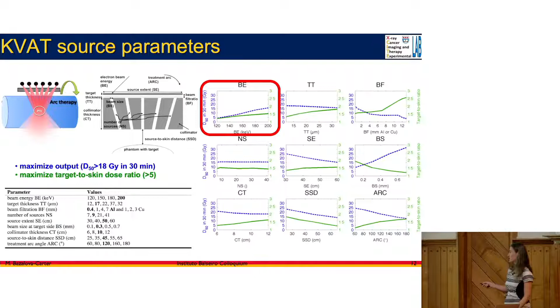But we basically concluded that beam energy played a big role. So this is just D50, maximized D50, maximized target to skin ratio. In green, D50 in blue. We found out that the higher the beam energy, the better the beam output, and the higher the target to skin ratio. So that wasn't surprising, right? If you go all the way to 6 MV or 15 MV, this is going to be even better, but we would have to use a different technology. So we knew we wanted to maximize that, but of course it comes at the cost of increased shielding.